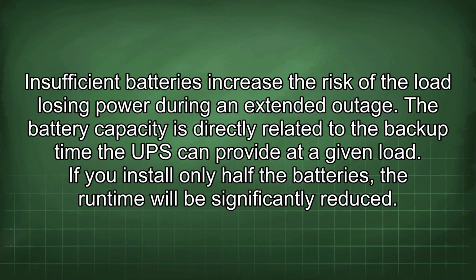Insufficient batteries increase the risk of the load losing power during an extended outage. The battery capacity is directly related to the backup time the UPS can provide at a given load. If you install only half the batteries, the runtime will be significantly reduced.